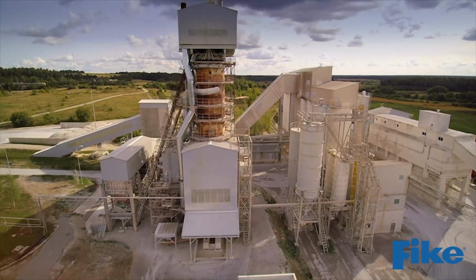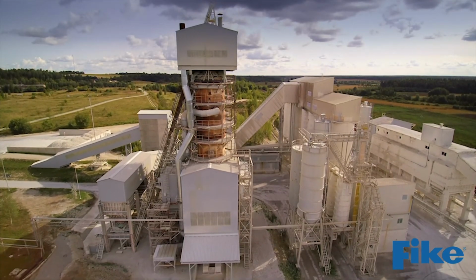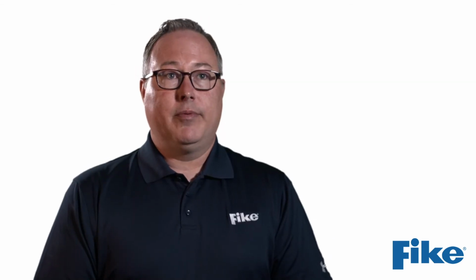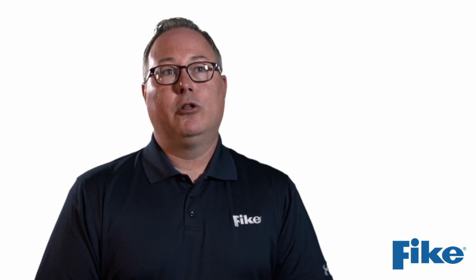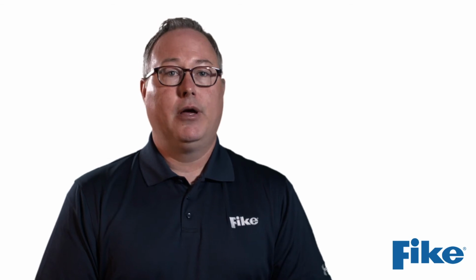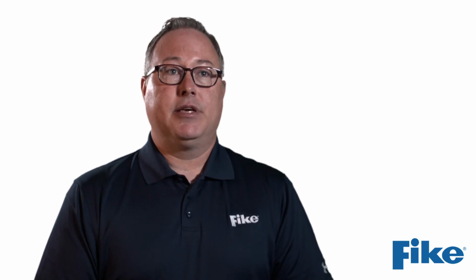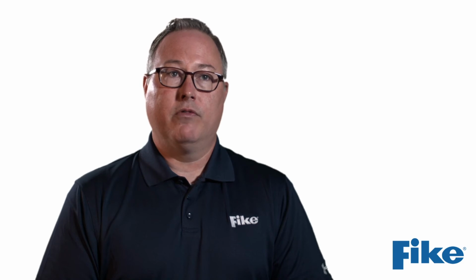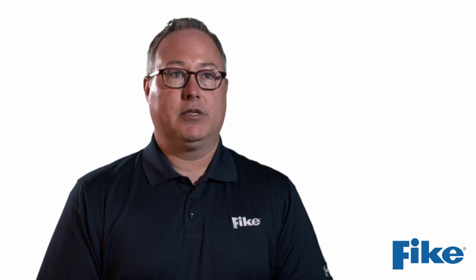It's important to have all of this information so that you can really understand how the equipment moves solid particles through it, because this is going to help you see where there might be ignition sources. This will tell you where inside the equipment there might be an ignitable dust cloud. And also, this documentation typically is included with the DHA. So I like to look at the DHA as a single place where you have all the critical information needed to understand fire and explosion hazards in your process.